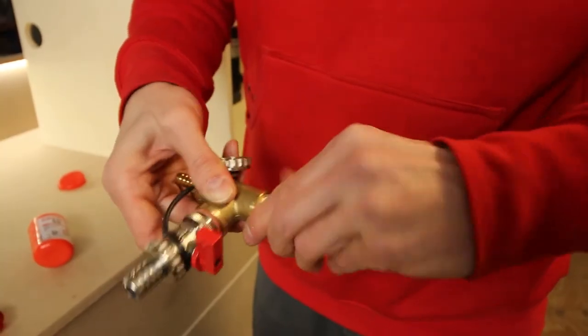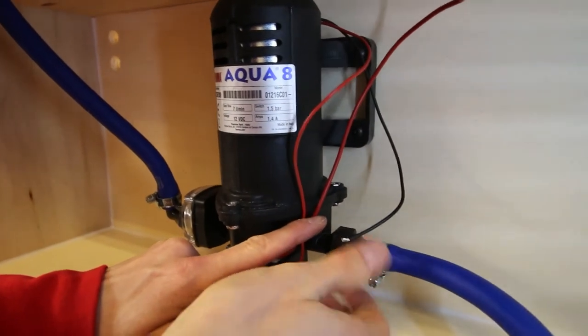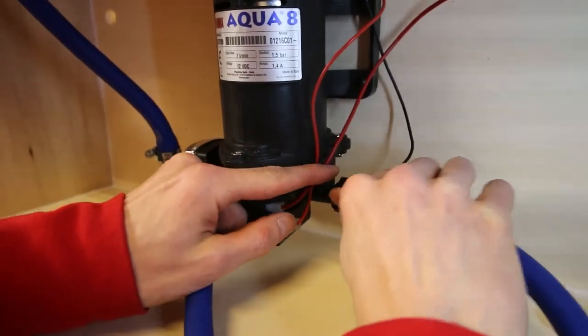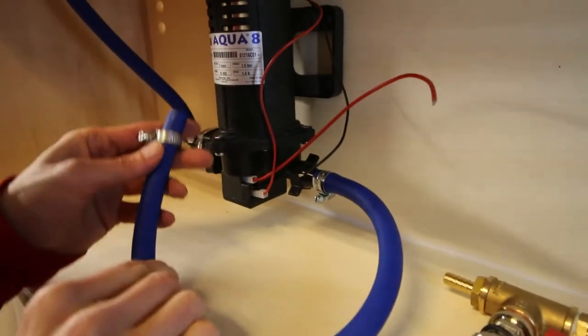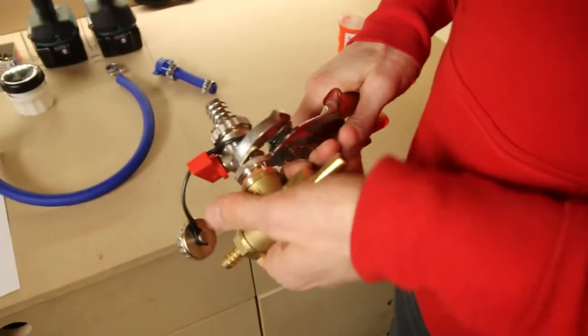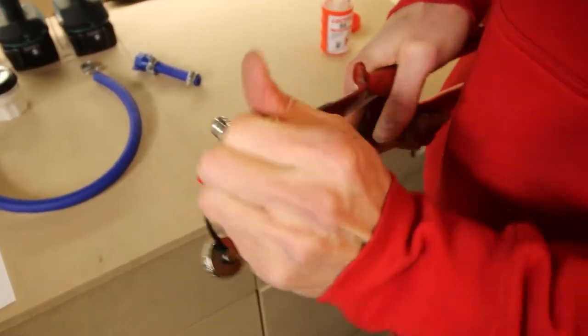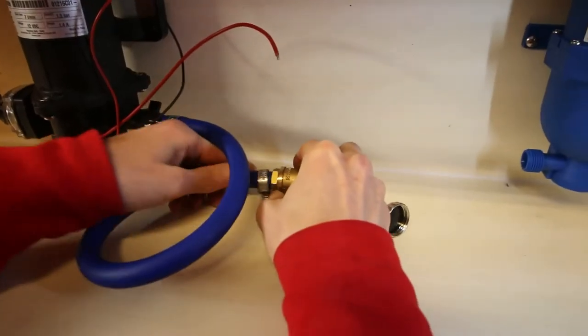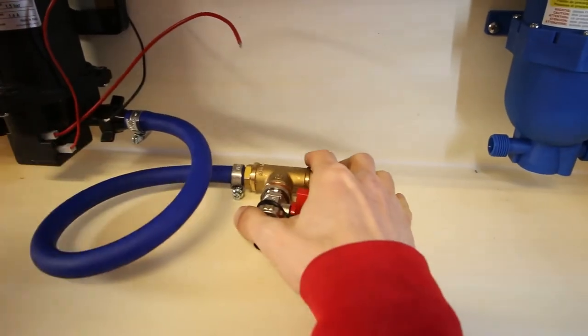The hoses between the water tank and the pump, as well as the pump and the expansion vessel, have a length of 0.5 meters following the pump installation manual. This length of the water hoses ensures that vibrations from the pump to the rest of the system are minimized.